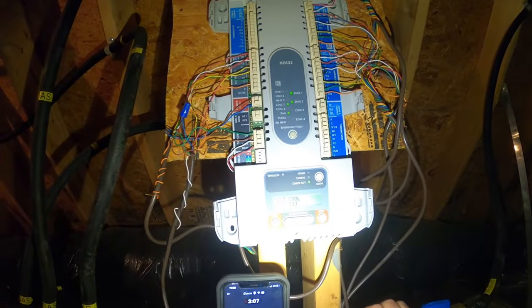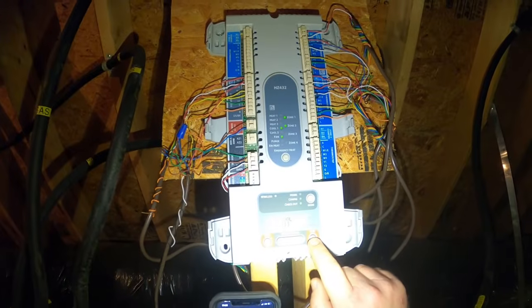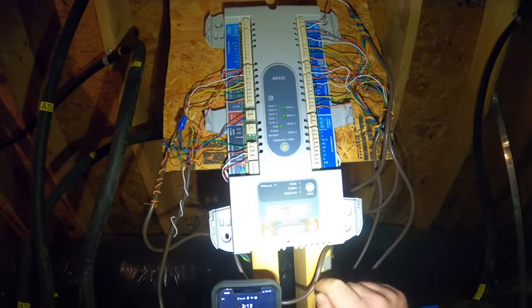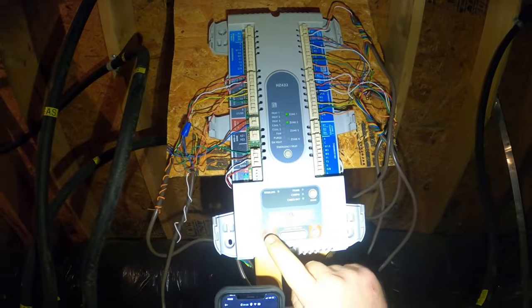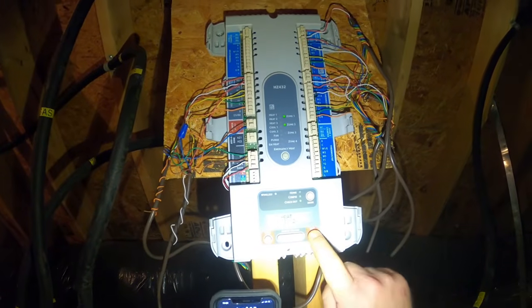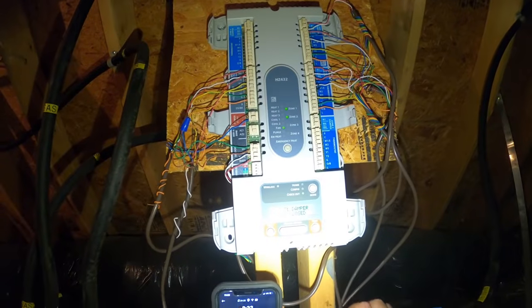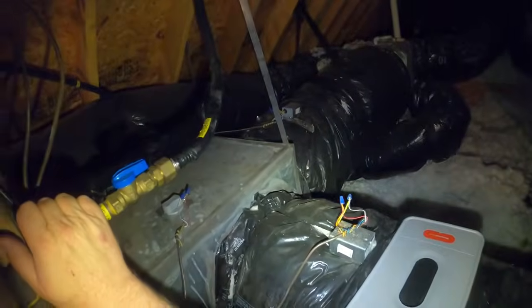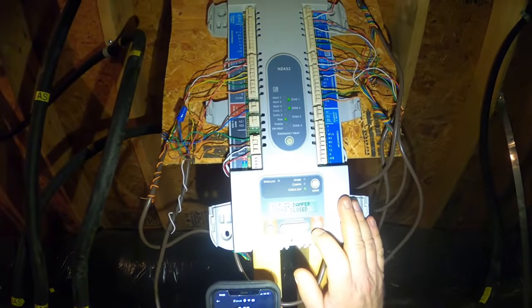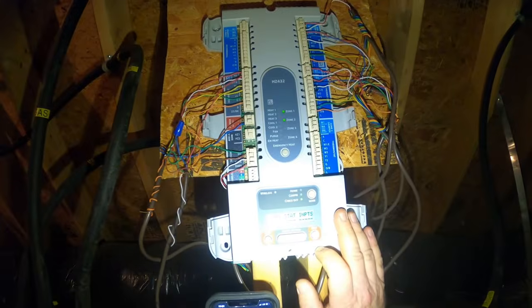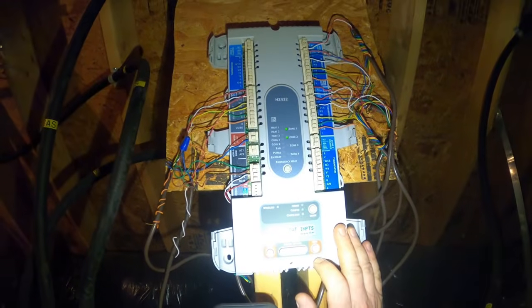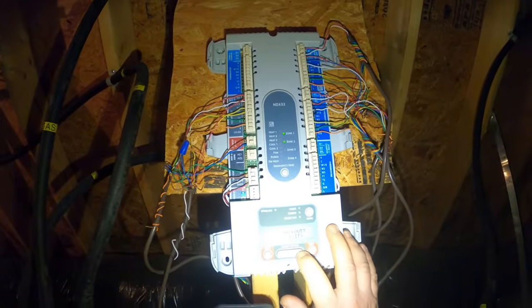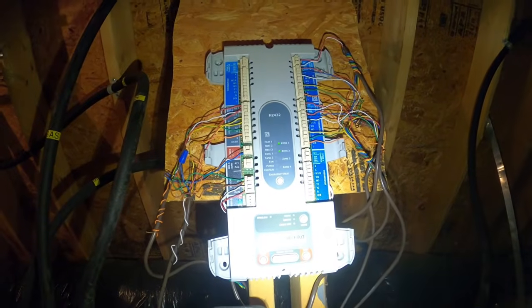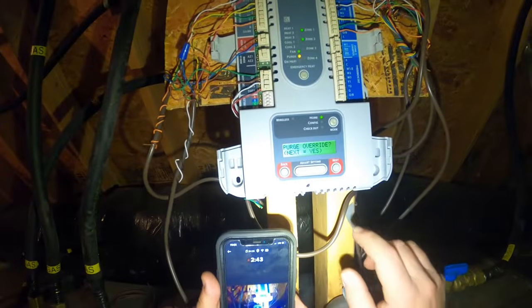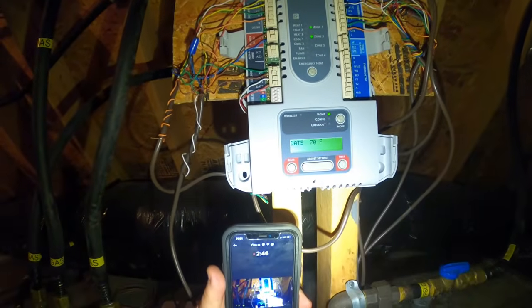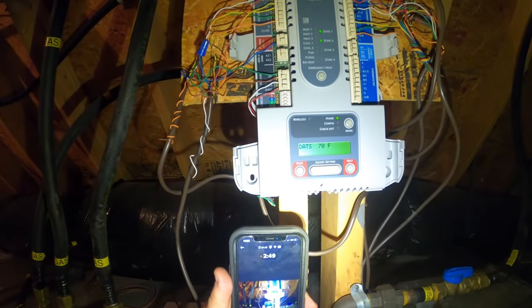Cooling 1, we have 1 stage of cooling. Test the fan. Fan's already running, but you can test it. So you make sure you go back and turn all these back off. Go through them. It'll cycle your damper motors one at a time. Zone 2. And then now we need to go hook up our thermostats. We're going to exit the checkout, and I'm going to go put those thermostats on the wall and see what they look like, change the settings on those, and then we're going to turn this thing on and go check the charge outside.